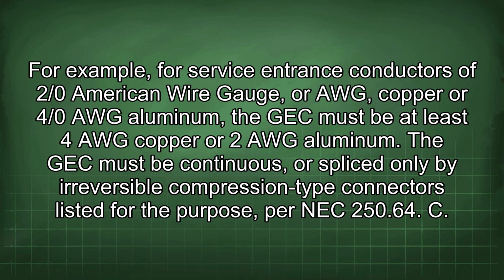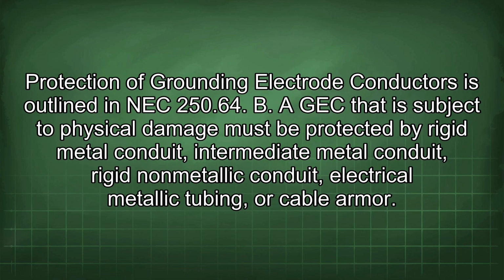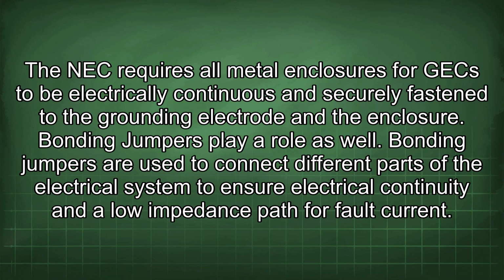Protection of grounding electrode conductors is outlined in NEC 250.64 B. A GEC that is subject to physical damage must be protected by rigid metal conduit, intermediate metal conduit, rigid non-metallic conduit, electrical metallic tubing, or cable armor. The NEC requires all metal enclosures for GEC to be electrically continuous and securely fastened to the grounding electrode and the enclosure. Bonding jumpers play a role as well.